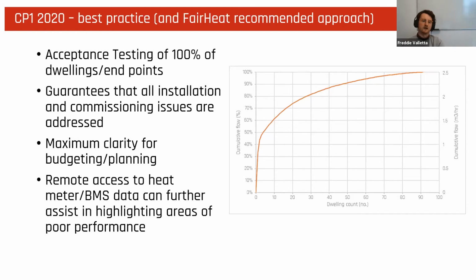So if we underwent acceptance testing on the 10% plus 10%, it's actually very likely that a lot of these poorly performing dwellings would have been missed in this approach, and therefore would have resulted in high flows and therefore high return temperatures and therefore poorer resident perception of the scheme. This really highlights that remote BMS and heat meter data can also be additionally used to ensure that the heat network is actually operating correctly and performance targets are met outside of this acceptance testing period.